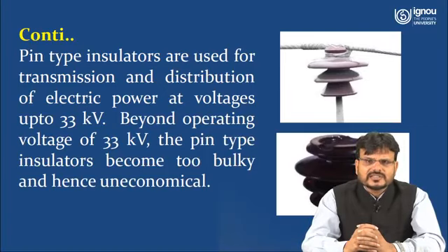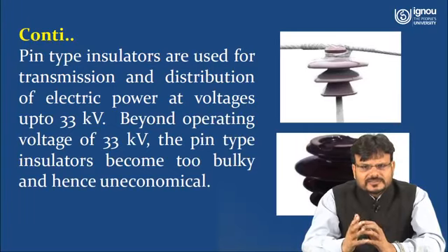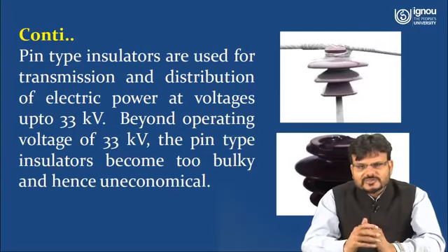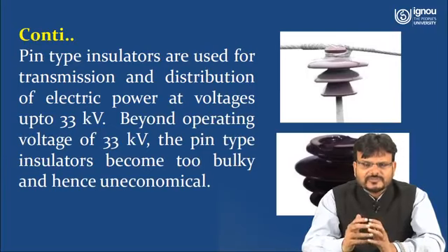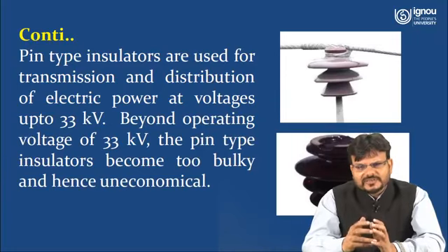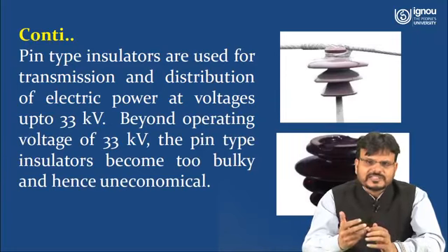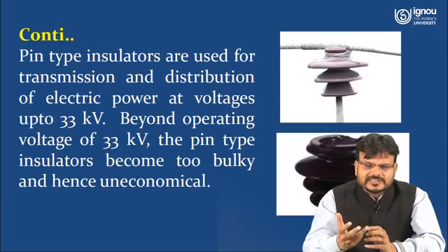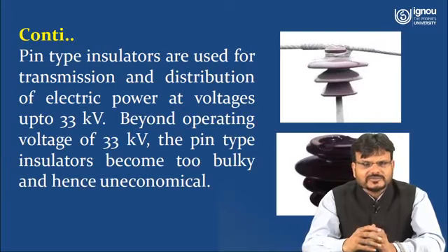Here you can see in the diagram that in this pin insulator there are 3 discs shown. So what is the function of these 3 discs? Basically it depends on the voltage. One disc is generally designed for 11 kV. Suppose you have to transmit or distribute power at 33 kV, that means you need 3 discs in this type of pin insulator. So beyond 33 kV, the pin type insulator is not economical.